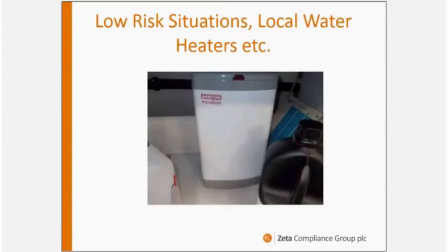Yeah, these low-risk systems, there's always been this question: is it a good idea to have a central hot water system and circulate the water, or is it better to have a decentralized system? Now, it's inherently safer to distribute cold water, because if the temperature goes wrong, if it reaches the ambient temperature, it's still only just in the incubating range. It's just going to warm up to 20 something, the low 20s. So cold water is inherently safer. When you want some hot water, heat it up locally.